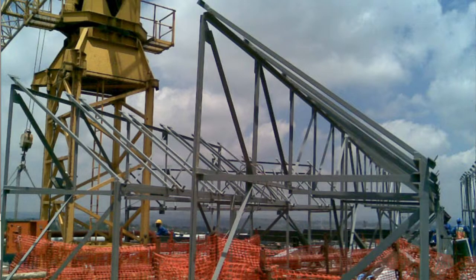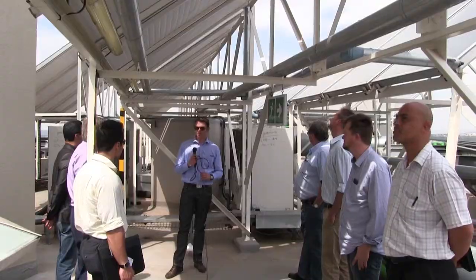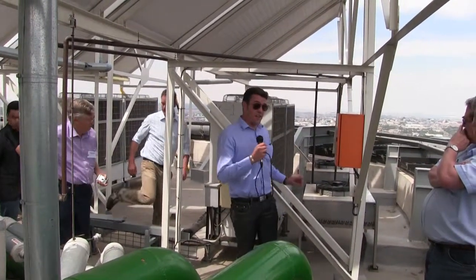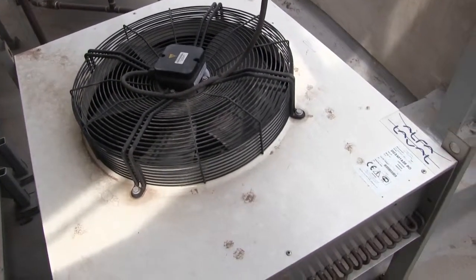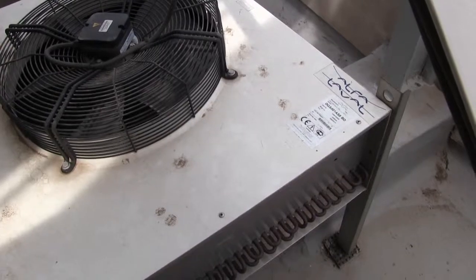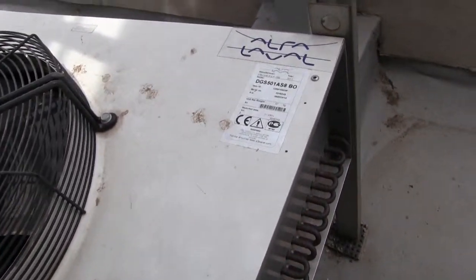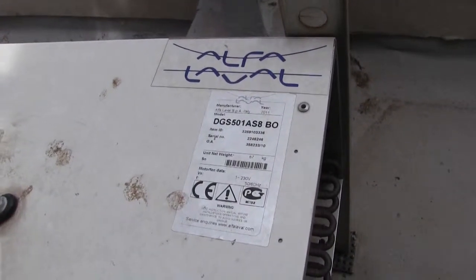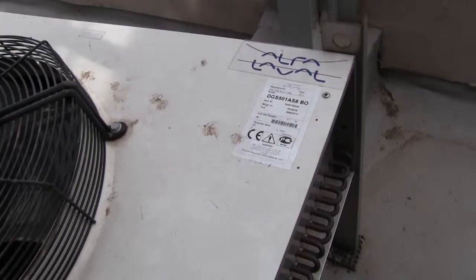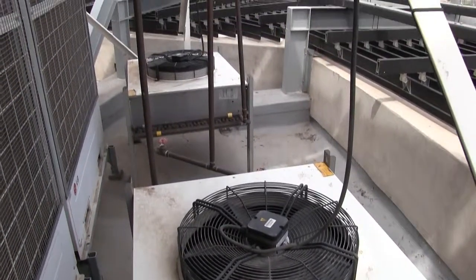Then let me go and show you the heat exchangers. Just look out for all the pipes. Okay, you can see the 2 heat loss radiators. They're activated with a temperature sensor down in the boiler room in the second last boiler. If it reaches 60 degrees Celsius, the heat loss radiator starts kicking in and cools it down, because it's a staggered approach in terms of the temperature in all 3 tanks. I'll show you a diagram downstairs as well.